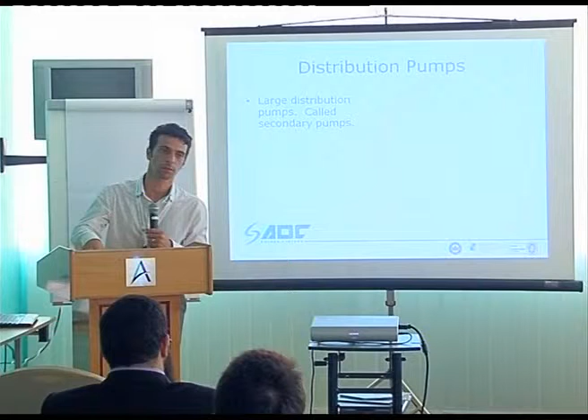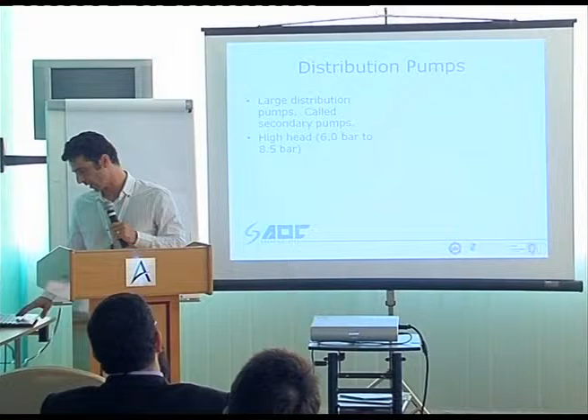Distribution pumps are the pumps responsible for taking the water all the way through the network and bringing it back into the plant. Because of the longer pipes, they are generally higher in kilowatts, because those pumps have to overcome a higher pressure in the network. Higher head, 6 to 8 bar.